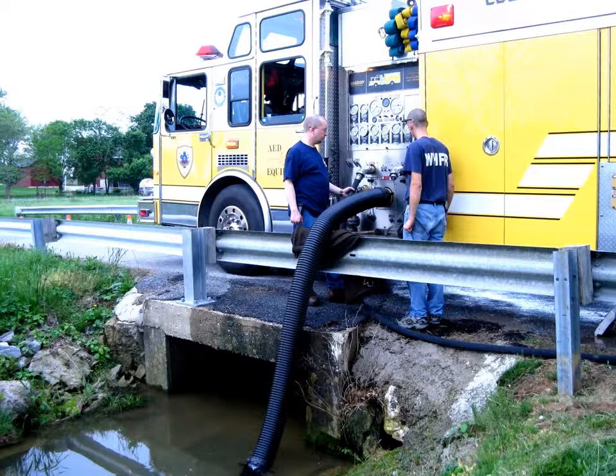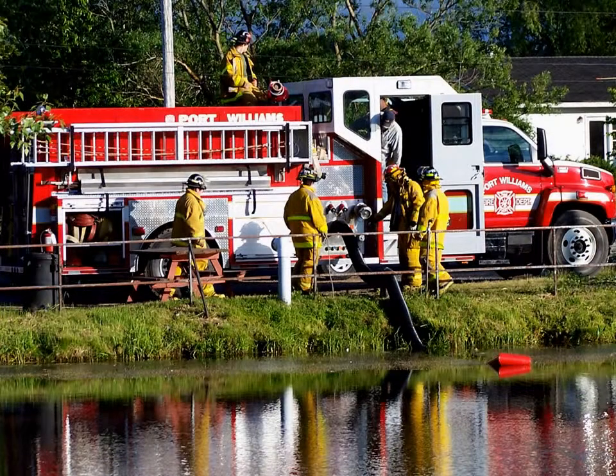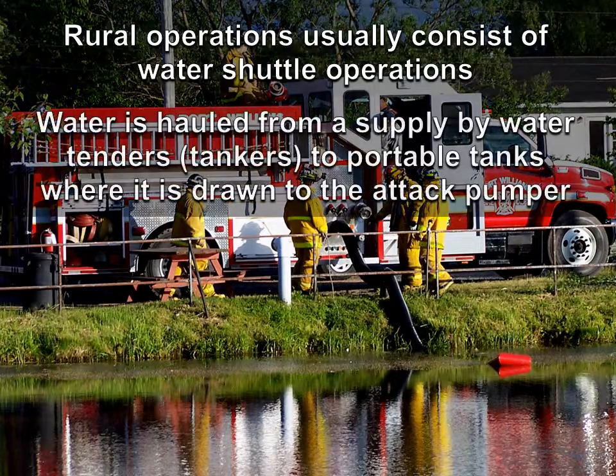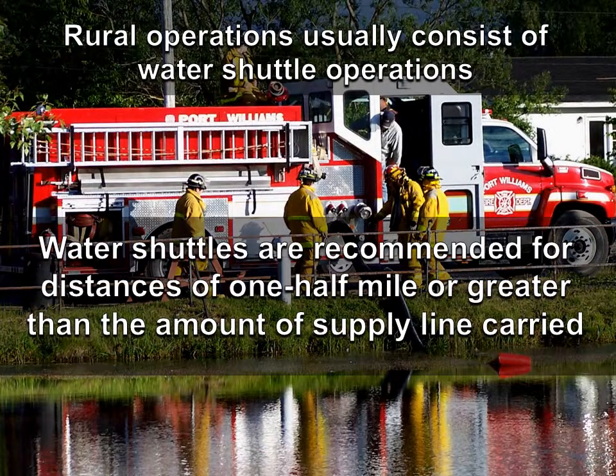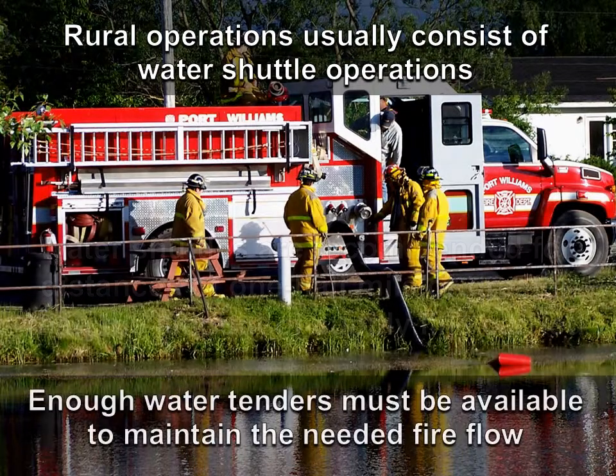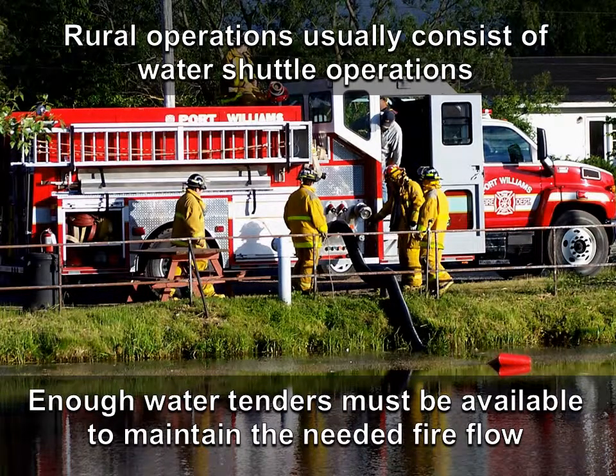Rural operations usually consist of water shuttle operations. Water is hauled from a supply by water tenders or tankers to portable tanks where it can be drawn for the attack pumpers. Water shuttles are recommended for distances of one-half mile or greater than the amount of supply line carried. Enough water tenders must be available to maintain the needed fire flow.